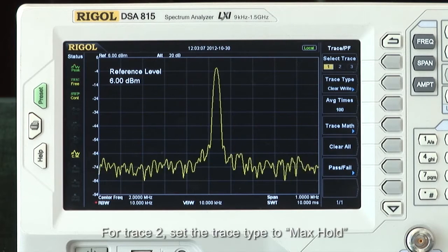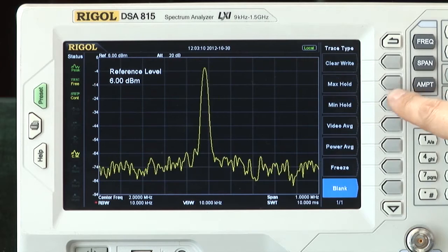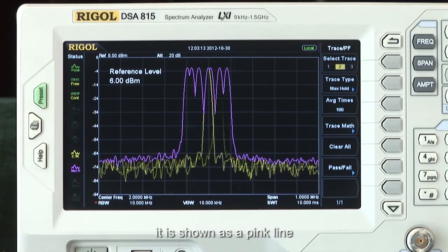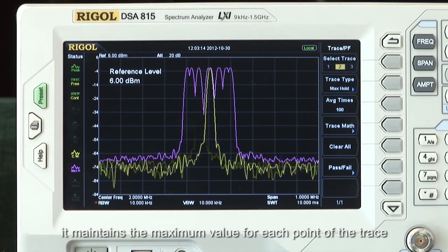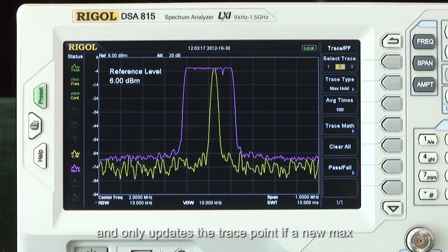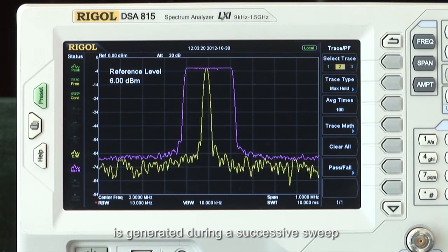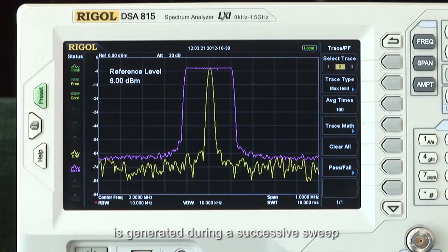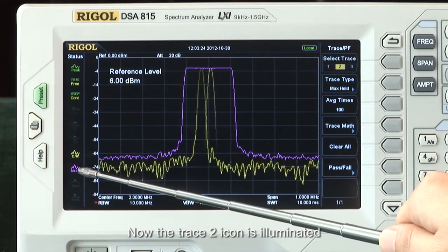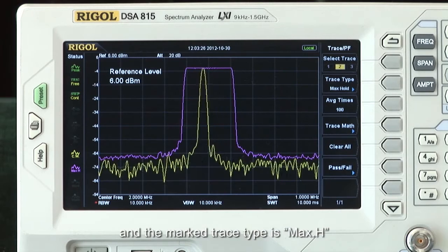For Trace 2, set the trace type to Max Hold. It is shown as a pink line and maintains the maximum value for each point of the trace, and will only update the trace point if a new maximum is generated during the successive sweep. Now the Trace 2 icon is illuminated and the marked trace type is Max H.